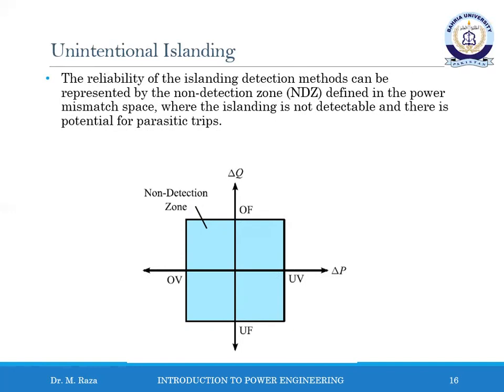The passive method has several advantages, such as low cost and a simple and straightforward structure, as only the mentioned voltage and frequency are used. This results in a large NDZ area which cannot be precisely determined in practice. However, in most cases, passive islanding detection is considered insufficient for AI protection in the distributed power generation system.